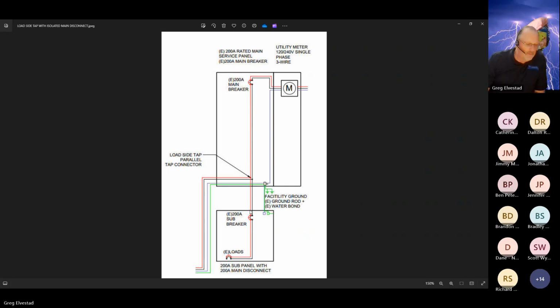Why? What you have is you have the capability of delivering power from the utility through this 200 amp breaker, and your PV source coming through this side to this tap point, let's just call it 40 amps for simplicity. All of a sudden you have the ability to deliver 240 amps down here to the loads.